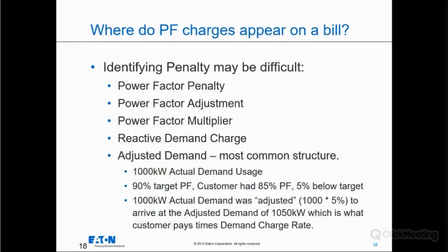So how do I know if I'm being penalized? Where do they appear on a bill? Well, identifying power factor can be quite difficult. It can actually be spelled out and say power factor penalty. I haven't seen that a whole lot, but it can say power factor adjustment, power factor multiplier, reactive demand charge, or it can be a little more hidden by saying adjusted demand, which is actually the most common structure in the United States. So in adjusted demand, how would that work?